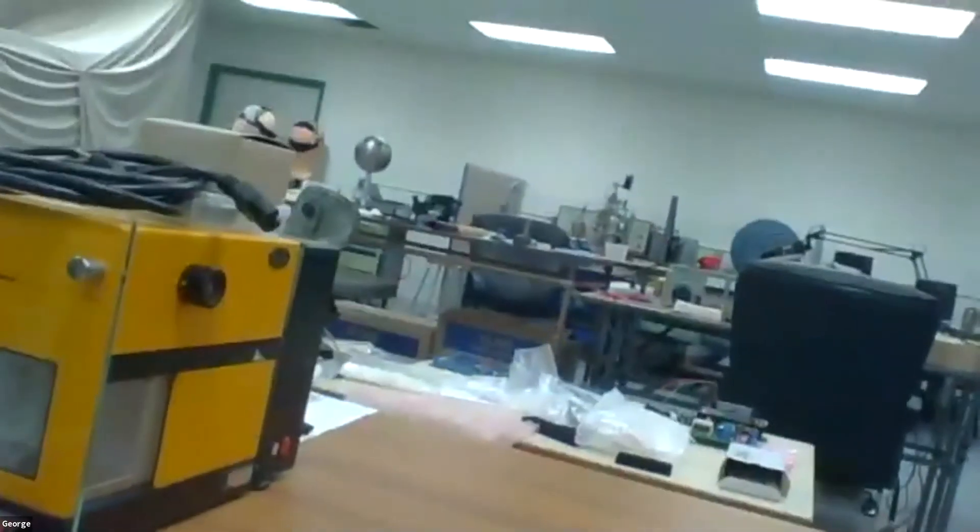This led to some concern that perhaps it would be beneficial to have an independent check on the calibration. So I was asked to put our apparatus to work. We have balances that are down to 10 micrograms — three of them actually — and then an ultra micro balance as well. The reason I had these Sartorius and Mettler balances was because I had put together one of the three, I guess, prominent test balances to look at Jim's ideas.